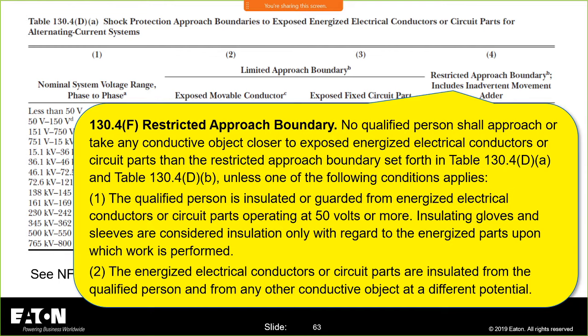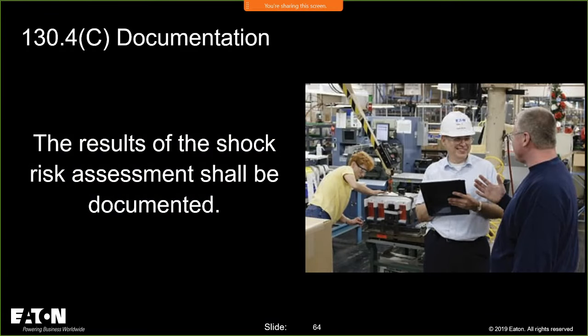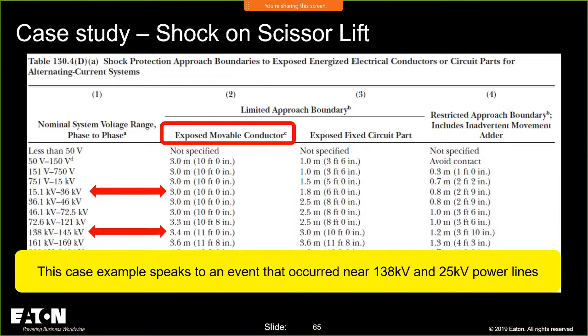A lot of people have your gloves and they're wearing short sleeves, but you've got to remember, you may turn and now your elbow comes in contact with something that's energized. So you want to use barriers, and barriers could be your personal protective equipment. They can be guards that you put up inside that equipment. You need to document that and make sure that you understand, and everybody understands on the job site, what the hazards are from a shock perspective.